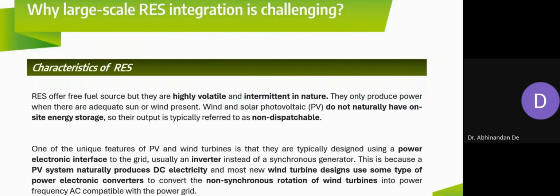We cope with the situation by, say, opening the steam governor, right? Or opening the valve in, say, hydro power plants, so that more water can pass to the penstock. But that takes time. The response time of these governors, valves, etc., may again be quite large, right? Because these are basically mechanical devices having a larger time constant. So what comes to the rescue then?